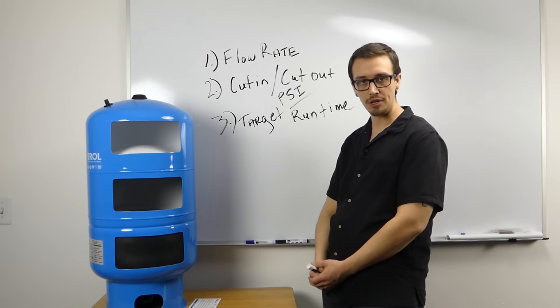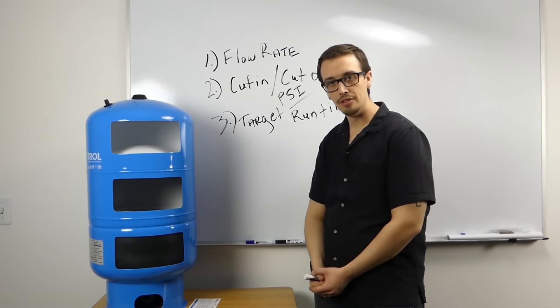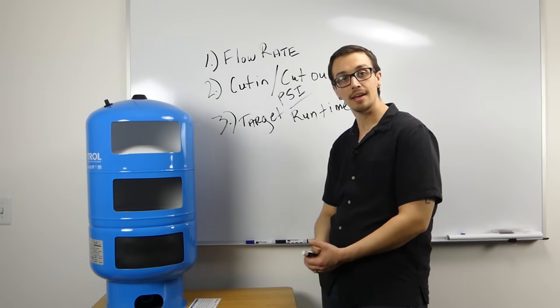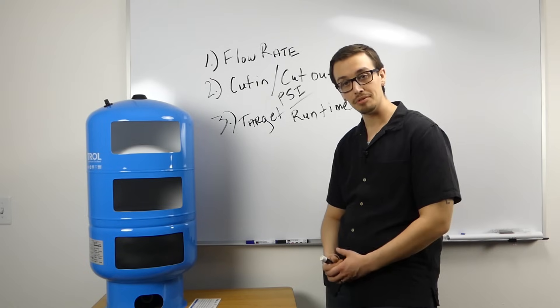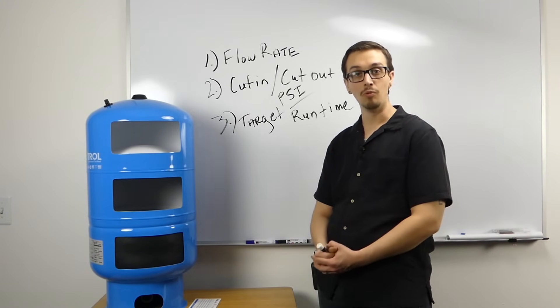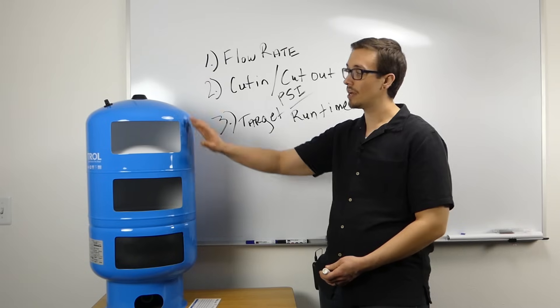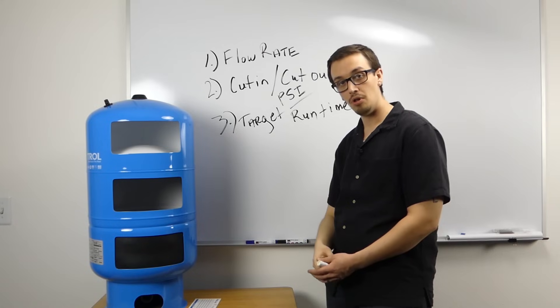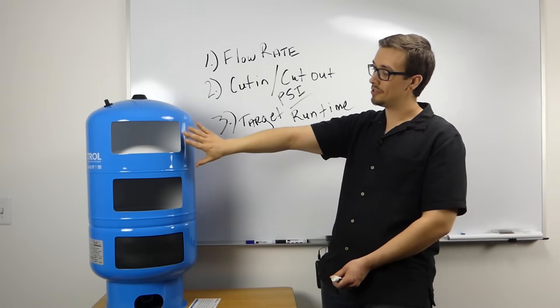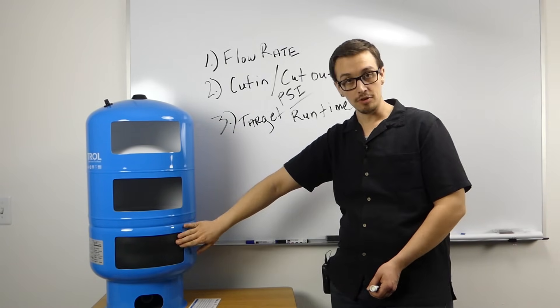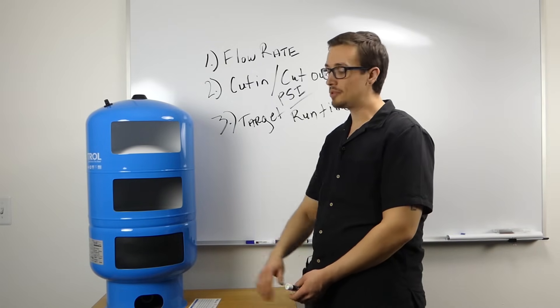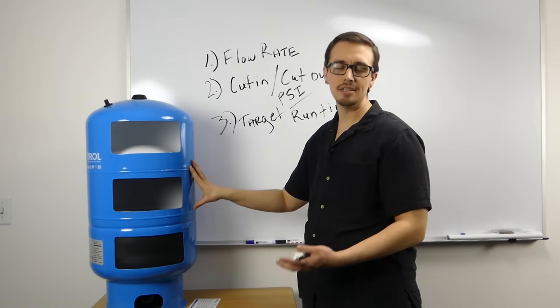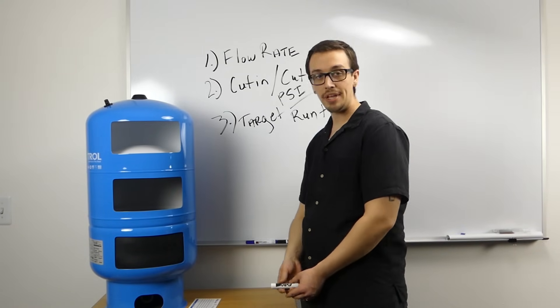One common misconception with pressure tanks is that the number of gallons of the tank is actually the drawdown capacity or the available volume of water in the tank. What I have here is a 20-gallon pressure tank, a Wellxtrol 202, and you can see that it's been cut out for display purposes. The volume of the tank does not necessarily match the drawdown capacity of the tank.